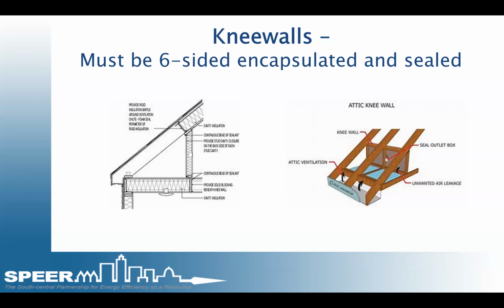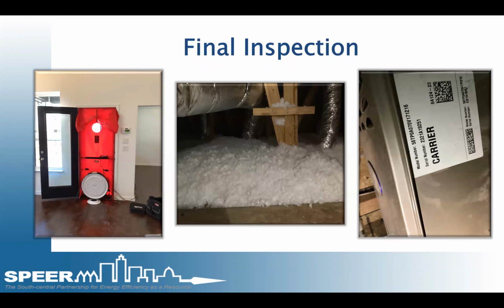So the higher the ceiling, the more it pockets at the top, the more that it starts pillowing down and starts reaching the conditioned space where the homeowner or occupant can feel it. Then they start adjusting the thermostats. So keeping those knee walls to a Grade 1 and airtight is absolutely essential.